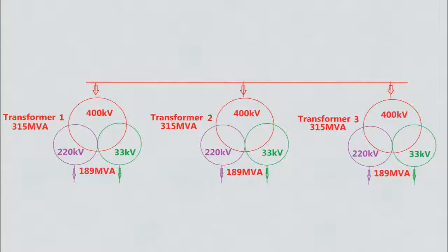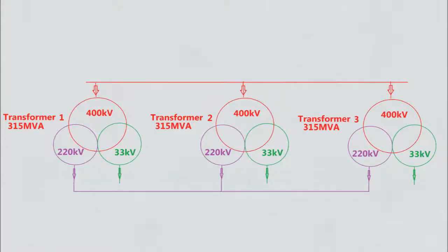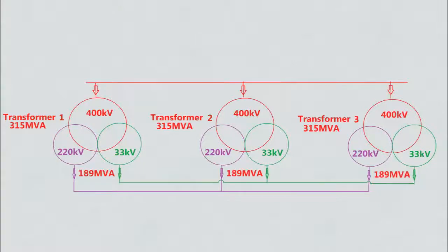Now, if we have to take Transformer 3 out of service for some work, this is the procedure we follow. First, connect all 220 kV sides of all 3 transformers, then connect all 33 kV sides of all 3 transformers — now the load is evenly distributed. Next, turn off the 220 kV and 33 kV side of Transformer 3, and then turn off the 400 kV side of Transformer 3. Transformer 3 will be out of service and its load will shift onto Transformer 1 and Transformer 2, giving 283.5 MVA load each.